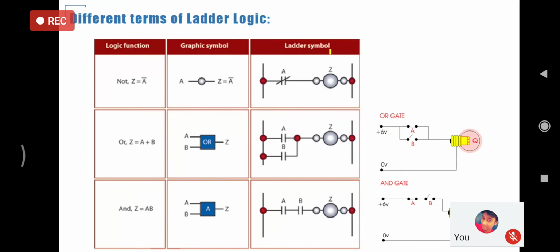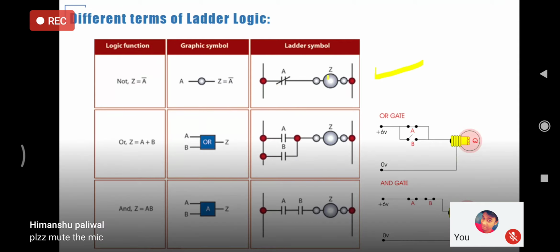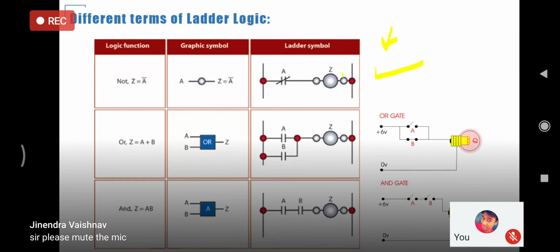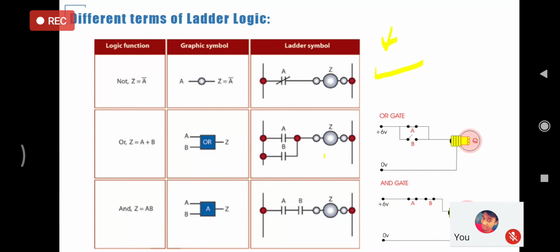Again, there are some more logics that can be performed using a ladder logic diagram in the field. We can also perform a NOT gate symbol. This sort of application from a PLC is used as a safety switch, where the whole process is to be stopped. Then rather than placing a hardwired, normally closed switch, this can be done using software-based PLCs.